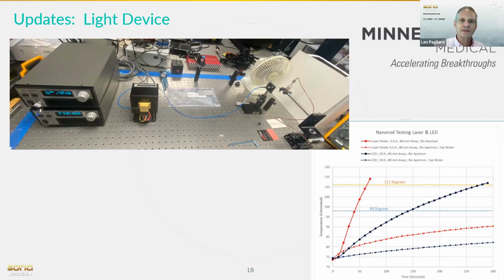One of the requirements is to get the infrared light through a long fiber. The fiber is going to have to be about 1 meter long, which is quite long. This would be the length of a colonoscope that again goes into the lower GI tract and can be manipulated by a doctor. These instruments have a free channel that you can put tools through. Very often it's a snare type device. In our case, we're going to put a fiber that delivers infrared light.